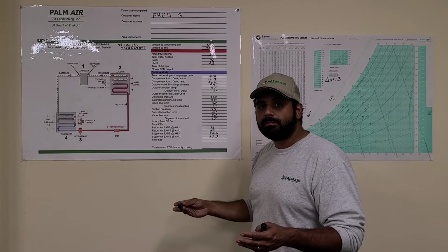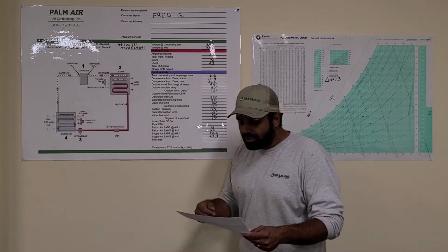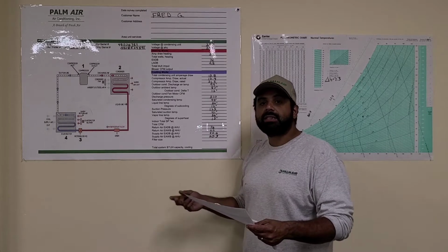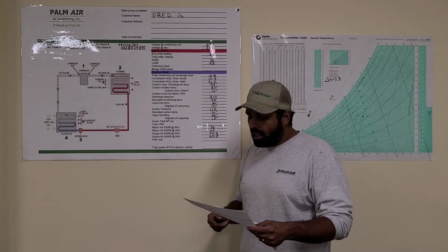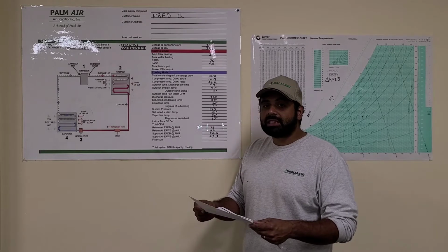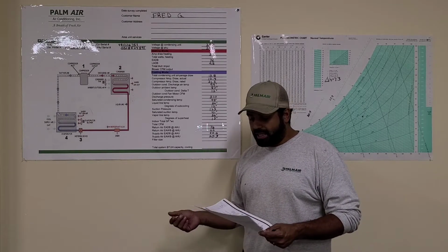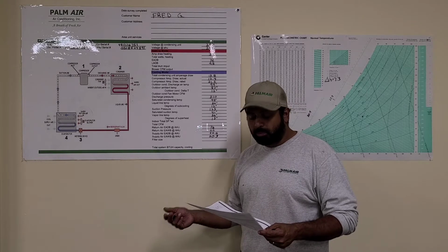I'll be right back. All right, gentlemen, I'm back. I've done the equation. 247 times 39 gives us 9,633. That's rounded, but that's 9,633 watts. We're going to go ahead and take that and convert it to BTUs heating.